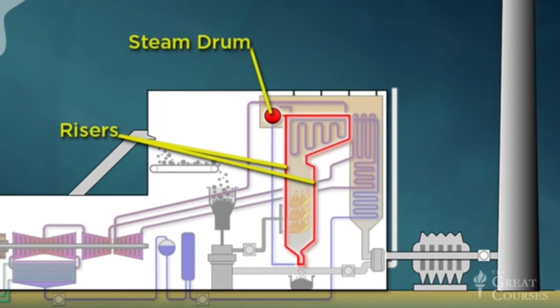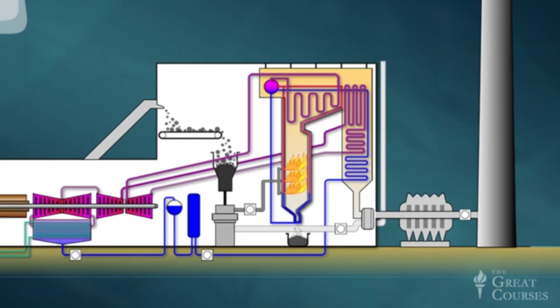Tapping steam from a vessel of boiling water might seem like a straightforward process, but when the vessel is fully enclosed and pressurized to about 2,600 pounds per square inch, it takes a centrifuge spinning inside the steam drum to segregate the light steam from the heavy water. The separated steam is now piped to the next stage of the power generation process. It's part of a larger closed loop that constitutes the steam power generation cycle, often called the Rankine cycle in the science of thermodynamics. We'll return to this cycle momentarily.